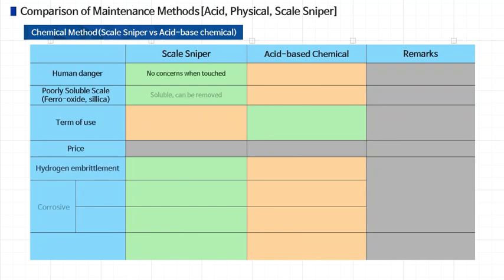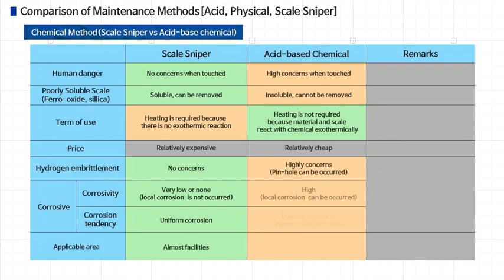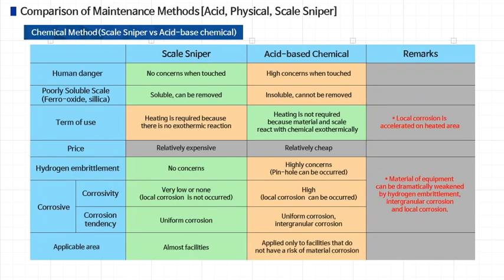This chart compares the pros and cons of the scale sniper and the widely used acid-based chemicals in chemical maintenance methods. The use of acid-based chemicals was extremely limited, as hydrogen embrittlement, local corrosion, and intergranular corrosion could occur, which could seriously damage the equipment.